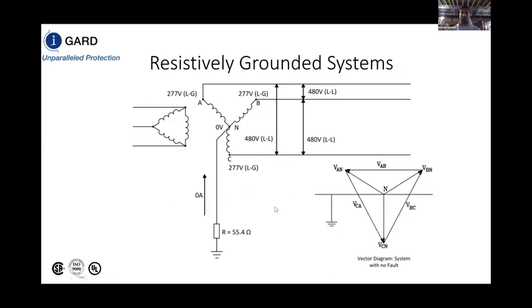So phase C ends up getting faulted, and the fault current will take the path through the resistance up to the neutral point and down through the C winding back to the point of fault, because current likes to close its loop. So now we have this circulating 5 amps of fault current.